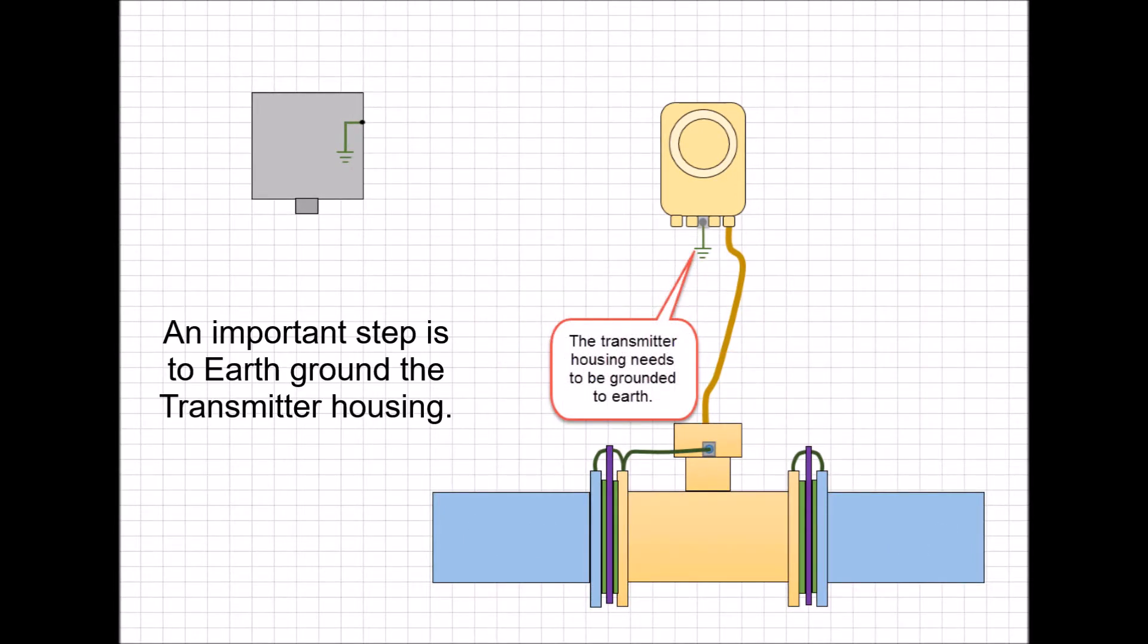In many installations the transmitter housing is left ungrounded. Many installations assume that bolting the housing to a metal frame is sufficient. It is not. The housing ground lug provides earth for the safety ground and equalizes the potential between the power source earth, the housing earth and the meter body. It also provides protection from surge events.